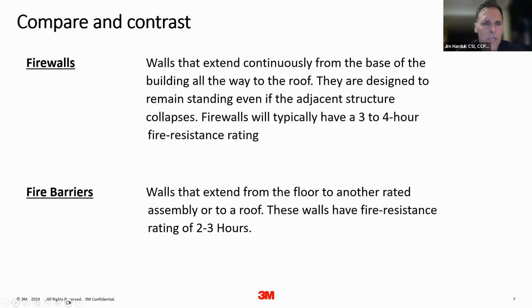Want to review some common terms in Firestop. First, I want to talk about firewalls. Firewalls extend continuously from the base of the building all the way to the roof. They're designed to remain standing even if the adjacent structure were to collapse. So when we're dealing with firewalls, we're typically talking about walls that are rated for 3 and 4 hours. So these are very robust structures. Typically, they're going to be constructed of CMU block or poured in place concrete. Next term, I want to talk about our fire barriers. These are walls that extend from the fire rated floor to another rated assembly or to a roof. These walls typically carry a fire resistance rating of about 2 to 3 hours. Typically, these walls are going to be constructed of steel studs and gypsum board, but they can also be wood frame constructed. Next slide, please.